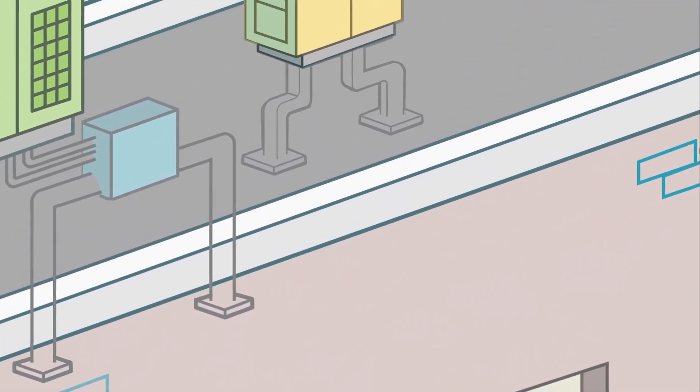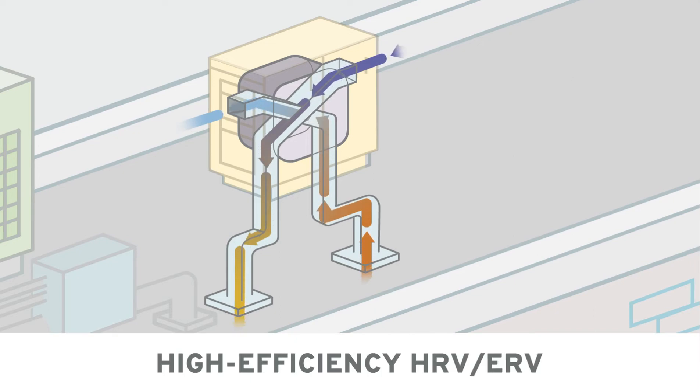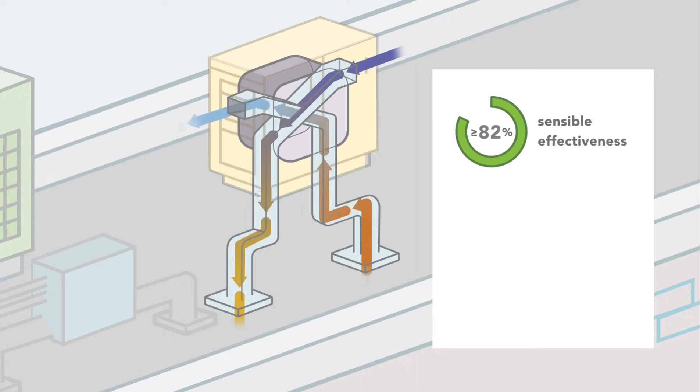Another important aspect of this approach is the inclusion of a high-efficiency heat or energy recovery ventilator that features 82% or greater sensible effectiveness. The high-efficiency ventilation system efficiently preheats incoming air by recovering heat from the outgoing exhaust air in the winter.